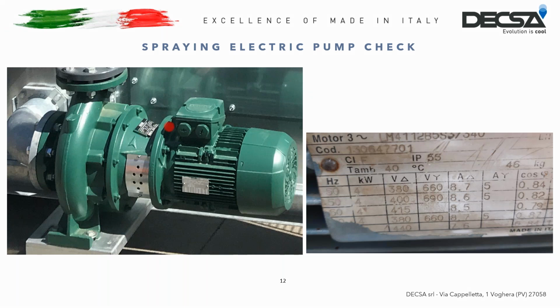It's a visual inspection aimed at checking there are no signs of wear in the casing and signs of scale or oxidation inside the terminal box after removing the cover of the same. Once this is done, with the pump running, it can be verified that the data resulting from the electrical panel to which the pump is connected, voltage, absorption, etc., correspond to those shown on the plate applied to the pump itself.